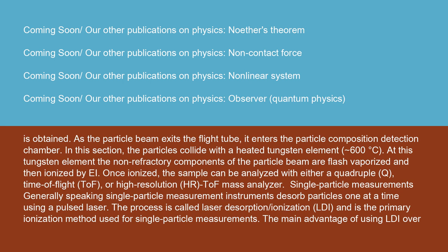As the particle beam exits the flight tube, it enters the particle composition detection chamber. In this section, the particles collide with a heated tungsten element at 600 degrees C, where the non-refractory components of the particle beam are flash-vaporized and then ionized by electron ionization (EI). Once ionized, the sample can be analyzed with either a quadrupole (Q), time-of-flight (TOF), or high-resolution (HR) TOF mass analyzer.